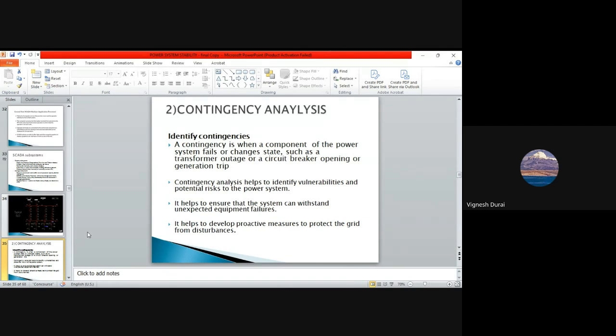Next, for contingency analysis, we have two things. Contingency is when a component of the power system fails or changes state, such as a transformer outage or the circuit breaker opening or tripping. Suppose any abnormalities happen, all your parameters will change, all your power flow will change. So if it is within the limit, no problem. If it is not, we have to analyze that.